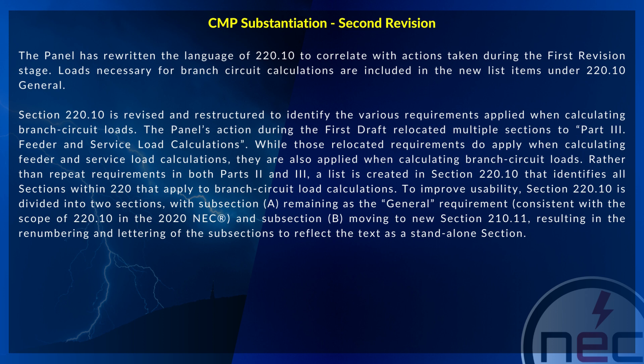The panel's action during the first draft relocated multiple sections to Part 3, Feeder and Service Load Calculations. While those relocated requirements do apply when calculating feeder and service load calculations, they are also applied when calculating branch circuit loads. Rather than repeat requirements in both parts 2 and 3, a list is created in section 220.10 that identifies all sections within 220 that apply to branch circuit load calculations.